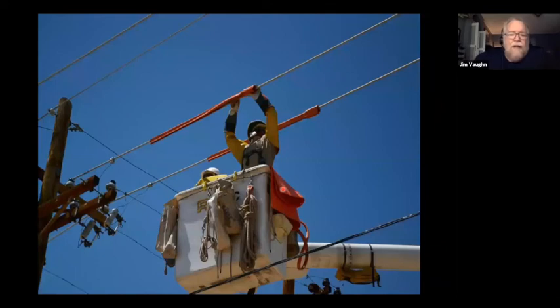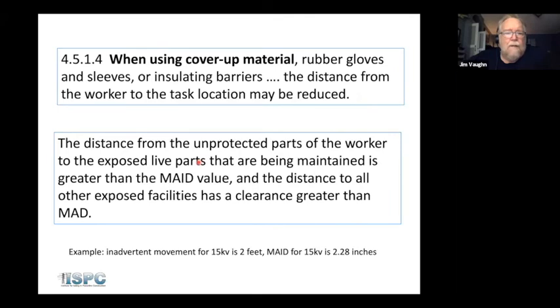And if you look at these guys, this again is a mistake. Now they covered up as they went in, but this is one of those environments where they're moving hose back and forth, because these guys working on this conductor are now within the MAD of the conductor that's behind them. That's a violation of the standard. Now we don't care as much that it's a violation of the standard, but the standard is there to keep you from getting killed. So they're not following the rules that are there to protect them, and we need to make sure that they do.